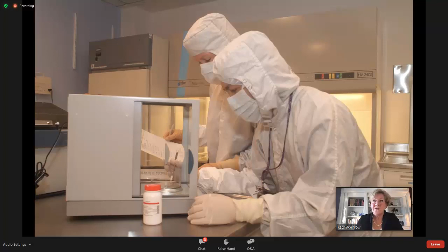It was an unbelievable laboratory. Class 100 design, we had a dedicated air handler, a sealed plenum, 30 air changes per hour, positive pressure, and live monitoring. We didn't know at the time, but this was going to be truly the gem of this laboratory design: live VOC monitoring.